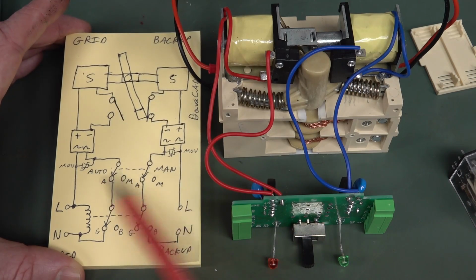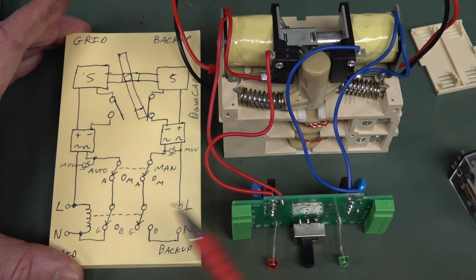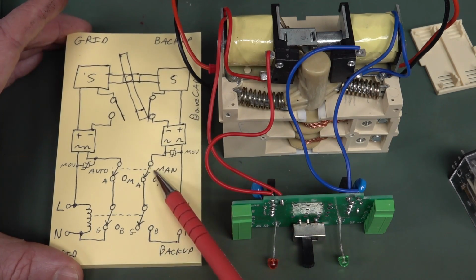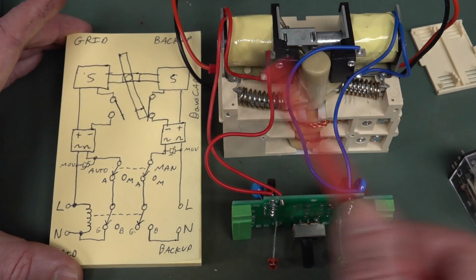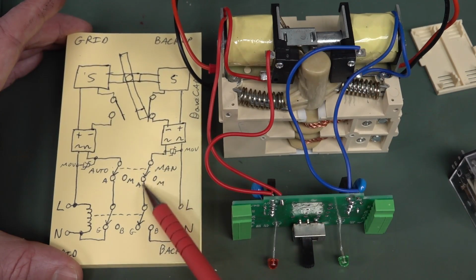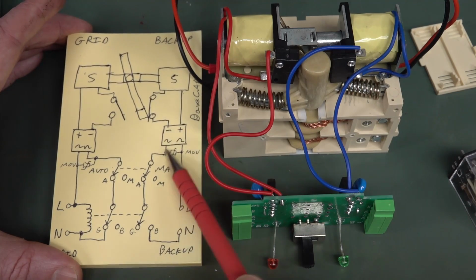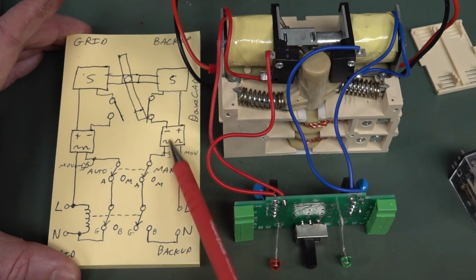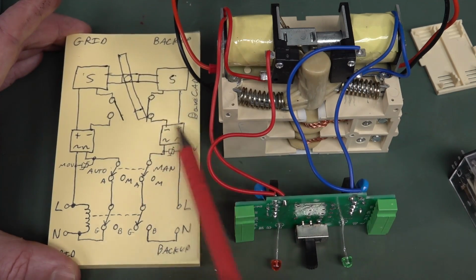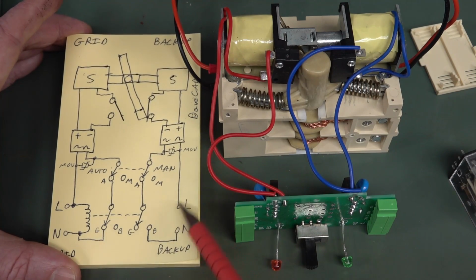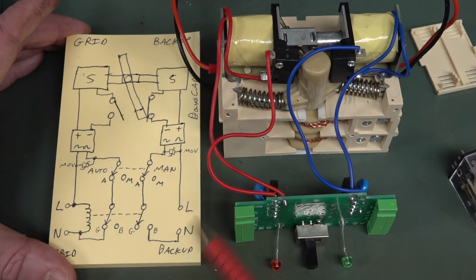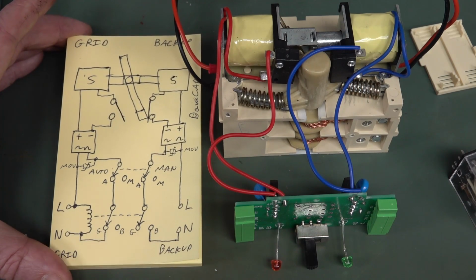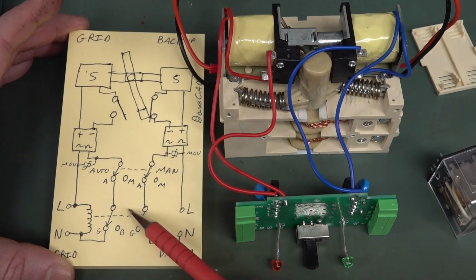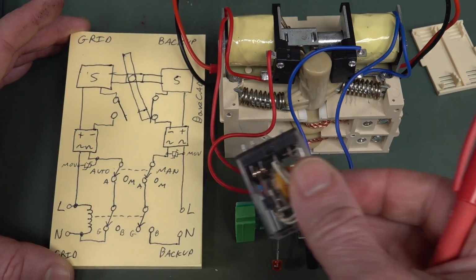Interestingly, it turns out that the auto manual switch simply disconnects the solenoids - it completely disconnects them. Once you put it in manual mode, you'll see it disconnects the solenoid. Each solenoid is powered via a diode bridge here, which is effectively straight across the mains. So this is the backup mains input, live and neutral, grid mains input, live and neutral here, and the relay is down here - that's this relay here.